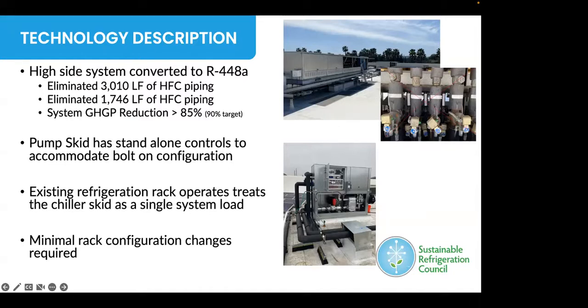So the picture on the top right is essentially the refrigeration rack house or weather pack that's on the roof. And the existing system here had individually circuited piping going out to all of the different cases in the store. And so what we put in was a standalone secondary glycol chiller. That picture on the bottom left actually is the pump skid, and it has integrated controls with it. So basically that pump skid is in a way a bolt-on approach where the existing refrigeration rack really just sees that chiller as a load on the system. And so we had to do very minimal upgrades or changes on the compressor rack to be able to use it.